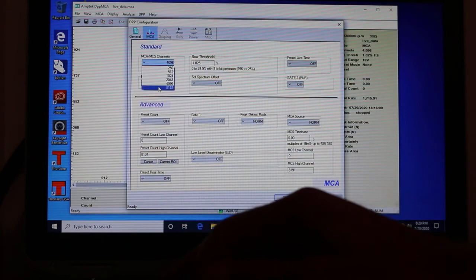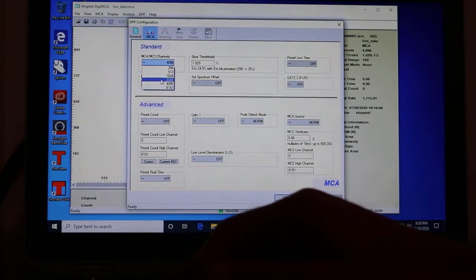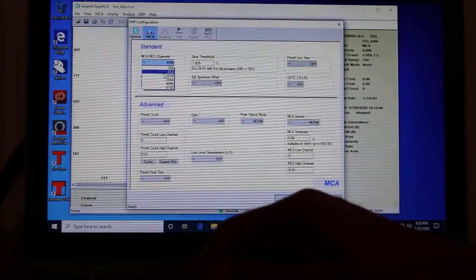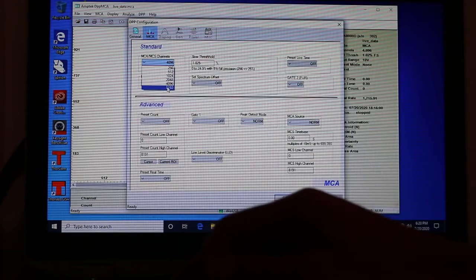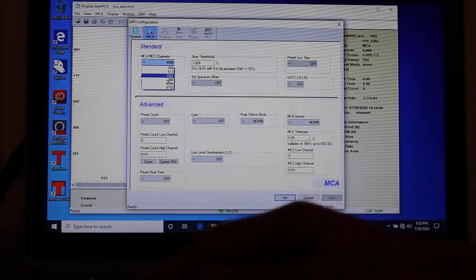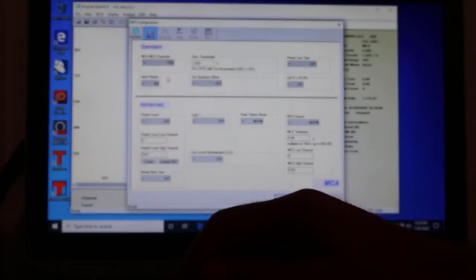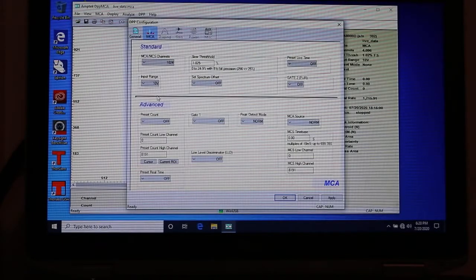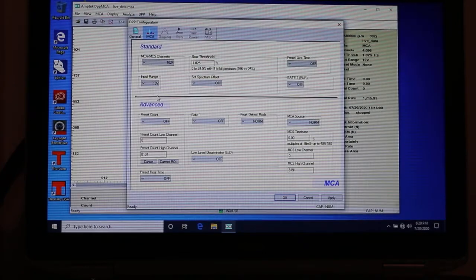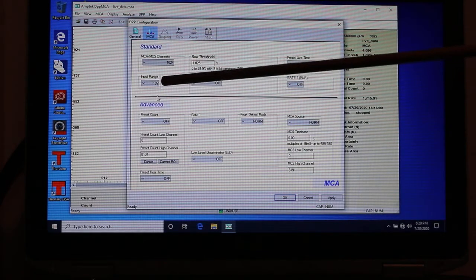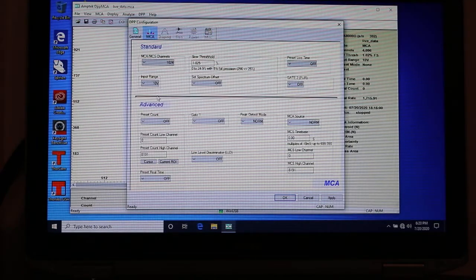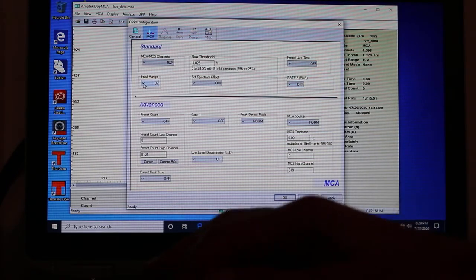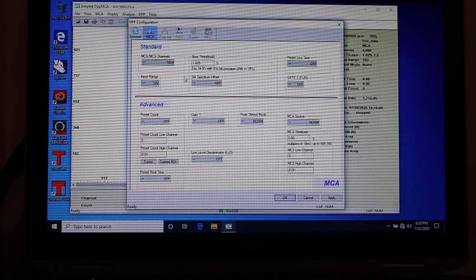I can go in here and change it to anything I want. 8192, 2048. These are the setting number of channels I can possibly have. I'll leave it at, well, let's just put it at 1024. So I decreased it, and I mentioned also at one point that the little black box here, the pocket MCA, takes inputs between 0 and 10 volts. There's a setting for that right there and that can also be changed if needed to 1 volt. But we won't do that. We'll go to 10 volts.